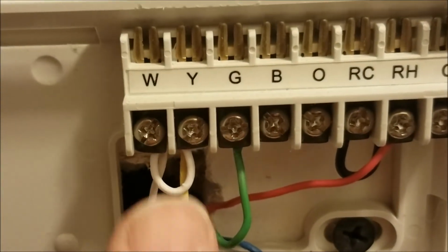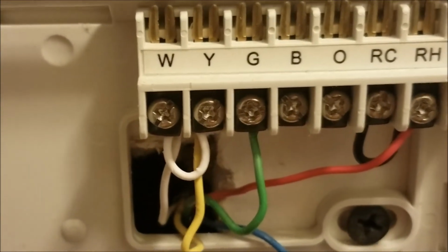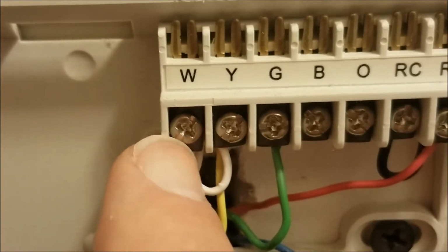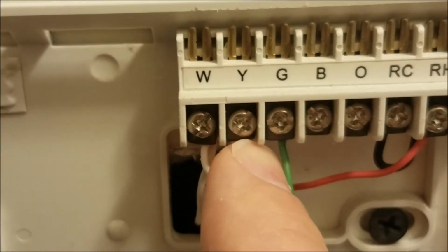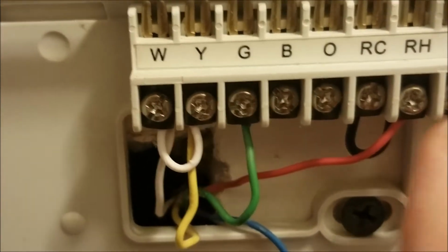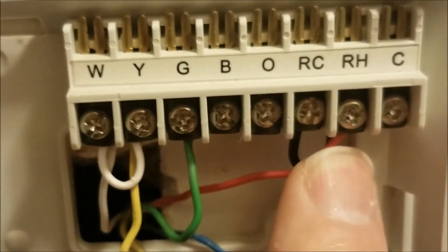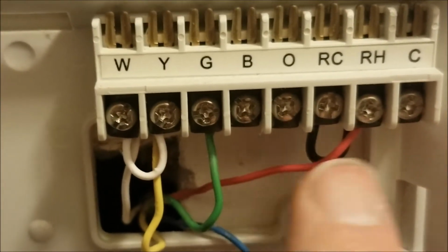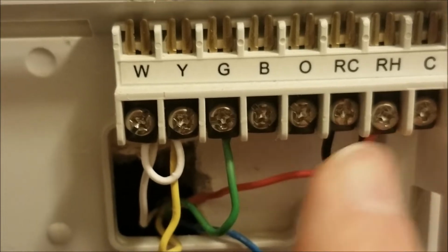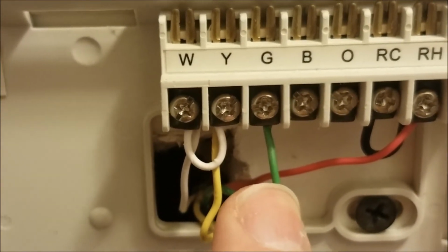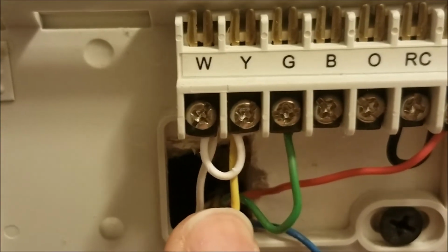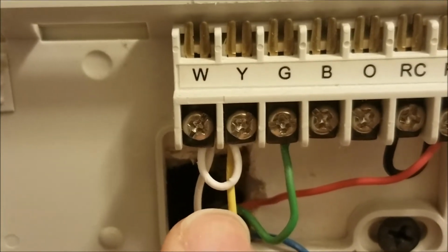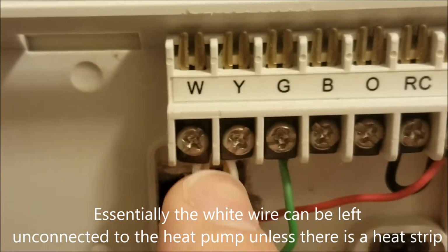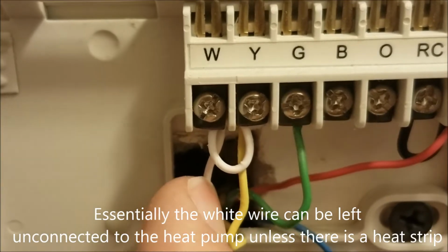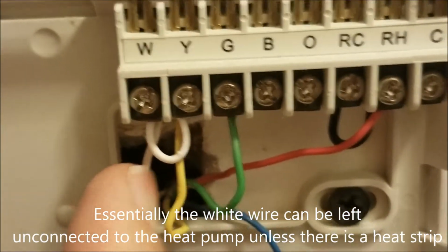And without this jumper in here, the compressor would never turn on. So at least for my thermostat, this is what it calls for: the W connects to the yellow, or the white connects to the yellow. So again, anytime you're calling for heat, this provides that 24 volts. Again, the switch turns the green wire on, and also the compressor, right? But the compressor's turned on with this white wire and this jumper. So this wire right now serves absolutely no purpose.